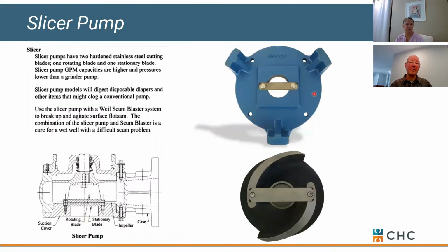Okay. Another style of pump is what we call a slicer. And this allows anything that comes into the pump itself to get sliced. You've got a fixed bar here on the inlet or the pump volute. You also have another fixed bar on the impeller, but that one's spinning. So anything that gets stuck between those two is going to get chopped into bits as it comes through.